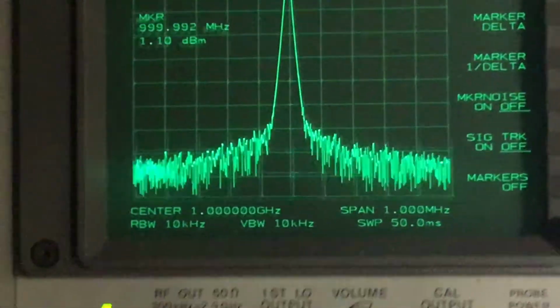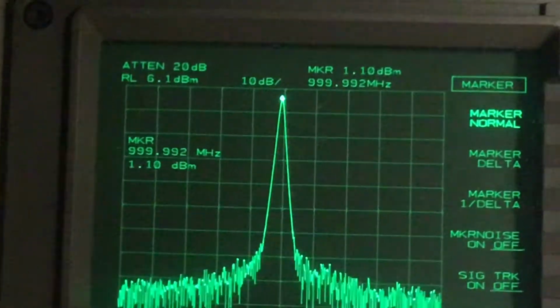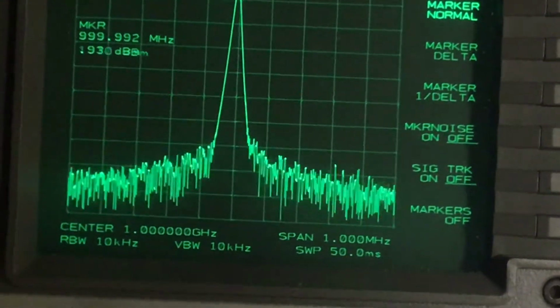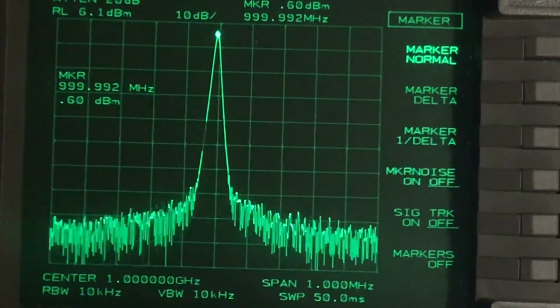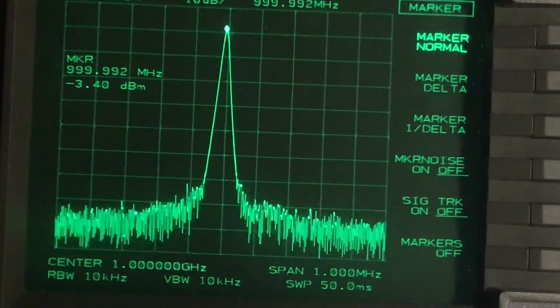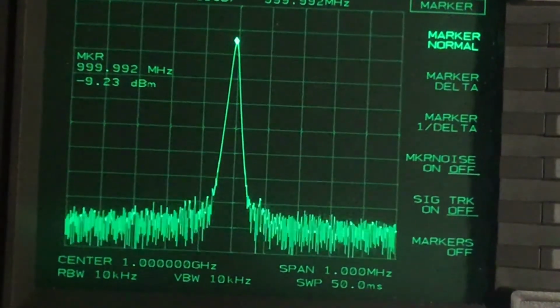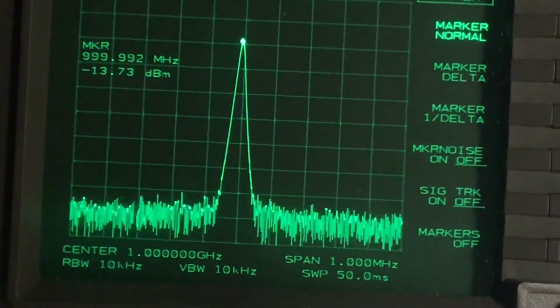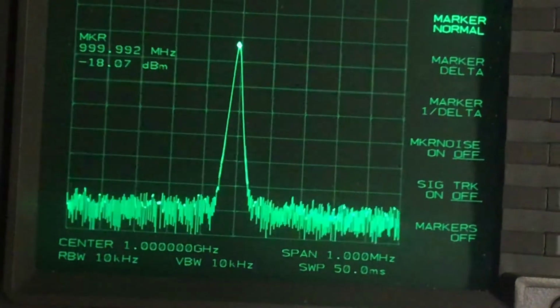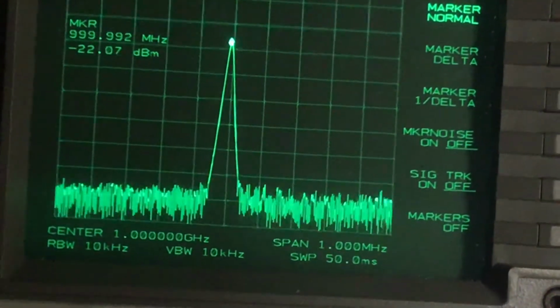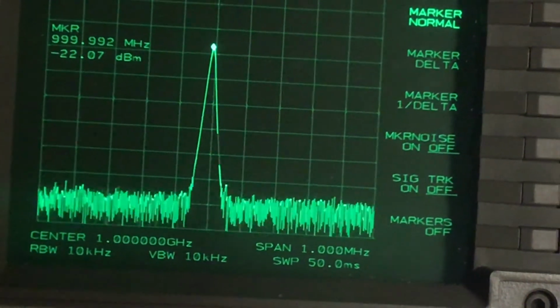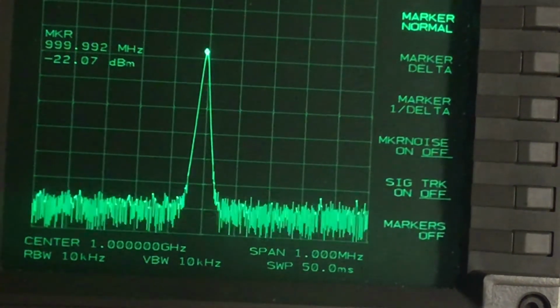But again, you can adjust the output level on the instrument, so I can set the output power. And because this has got the step attenuator on it, it can go really low in RF power. Just like a radio test set would have, like a Marconi 2955, you can adjust the RF level as well as pulse it. So again, there's quite a bit to it. It's a very nice instrument. You can do a lot with it, very capable, and it's one of these things that's nice to have around in the workshop.